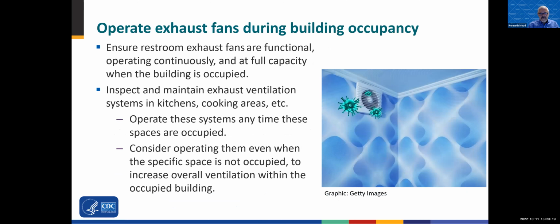Other exhaust fans in the building during occupancy might also be operated. I'm talking about bathroom exhaust fans that, in some systems, are only triggered when the room is occupied. Well, there's still some contaminant floating around in that room after occupancy ends. So let's allow those fans to keep exhausting air from that room, at least for a while after occupancy, and that'll help flush that air out. You can also get protective air flushing by keeping kitchen exhaust system fans running longer than you might normally.